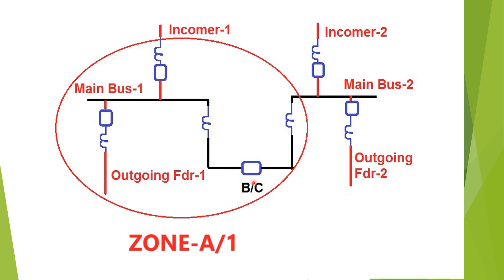There are two zones of bus bar protection relay — zone A and zone B (zone 2). Zone A or zone 1 is formed via outgoing feeder one CT, incomer one CT, and the CT connected towards the main bus two side of the bus coupler bay. If a fault occurs within this zone, these three breakers will be tripped and the fault will be cleared.